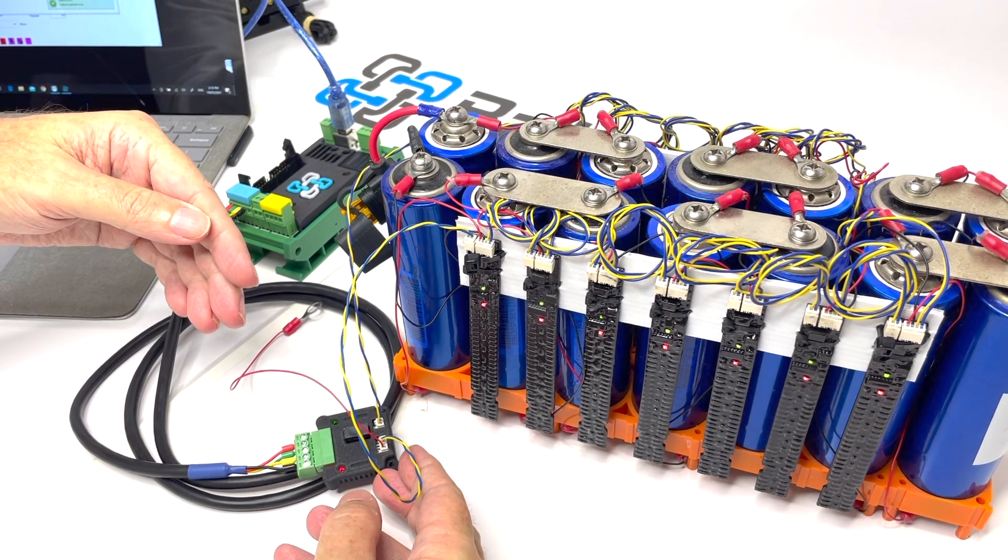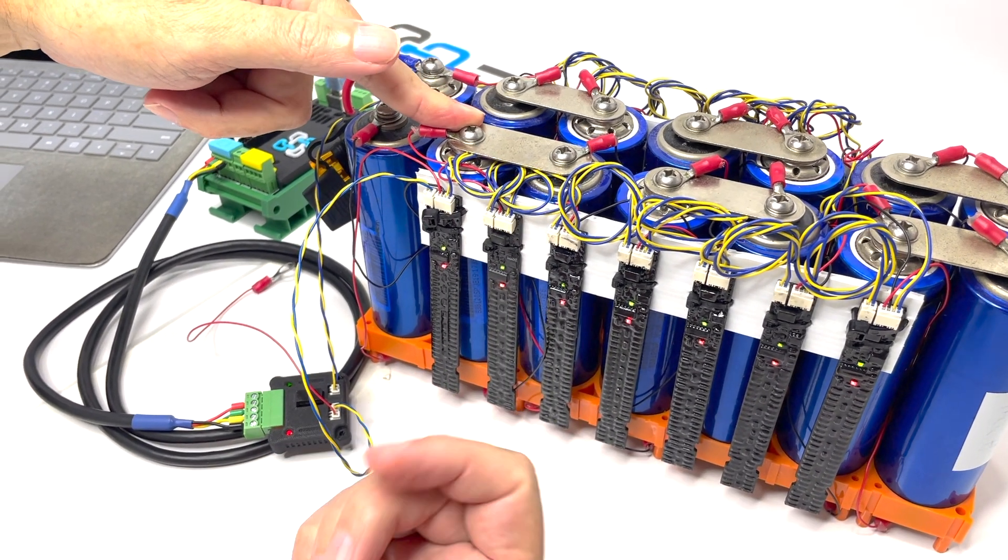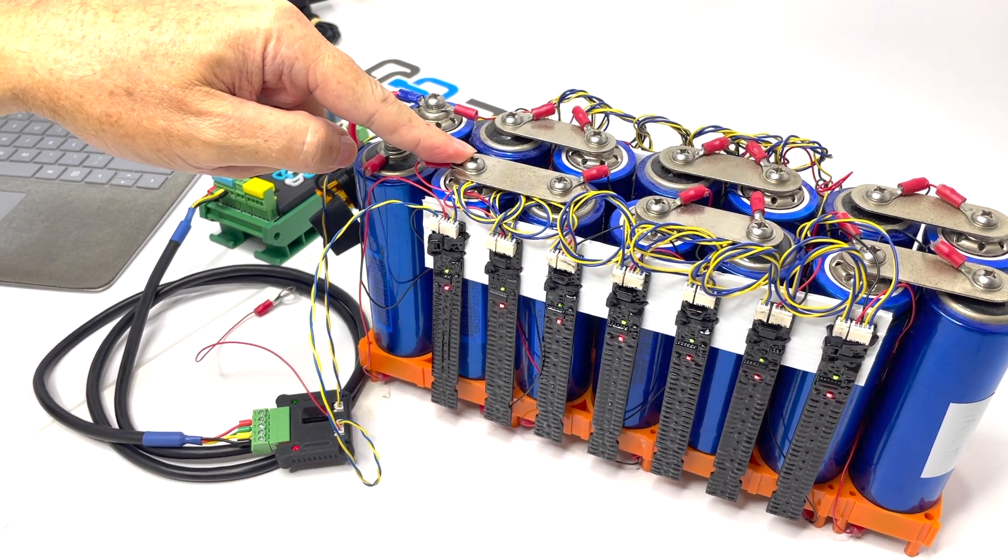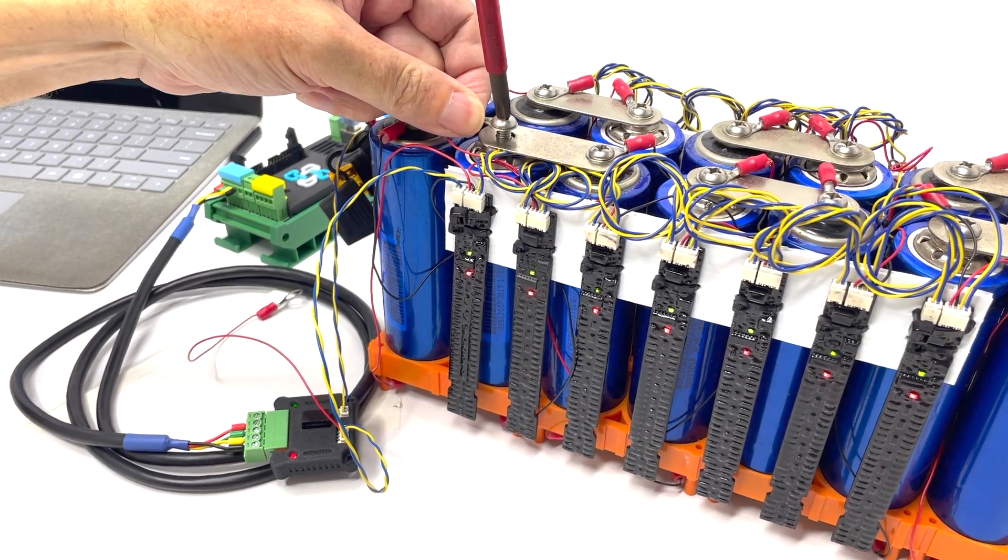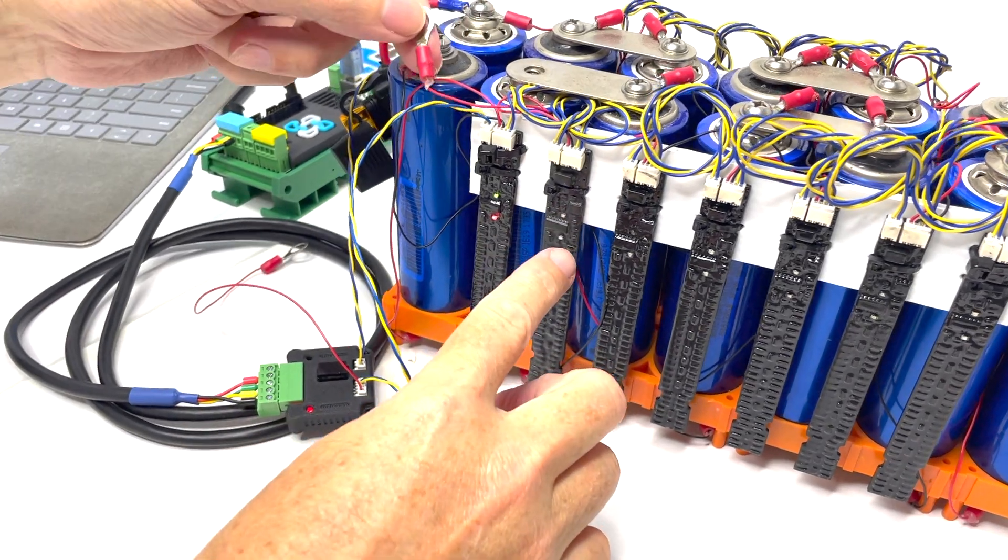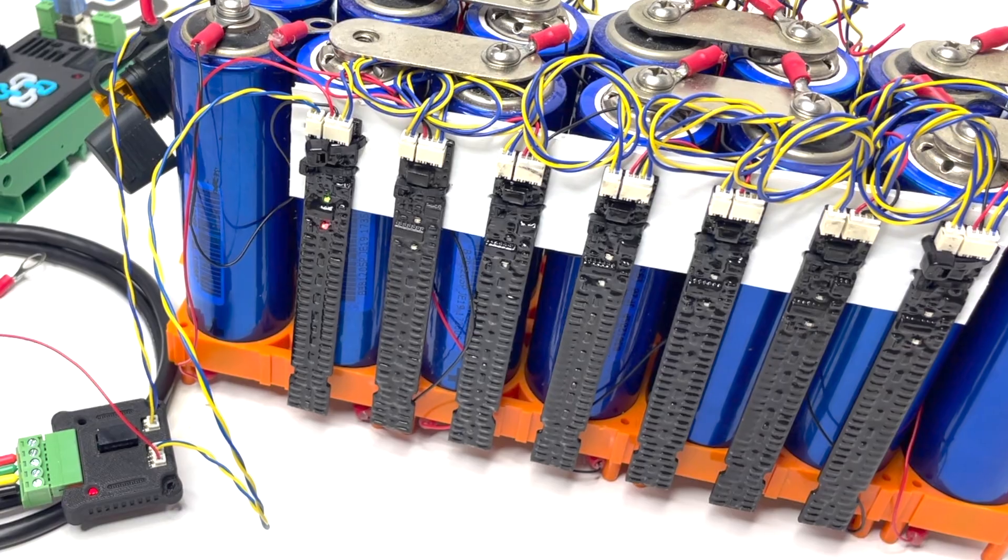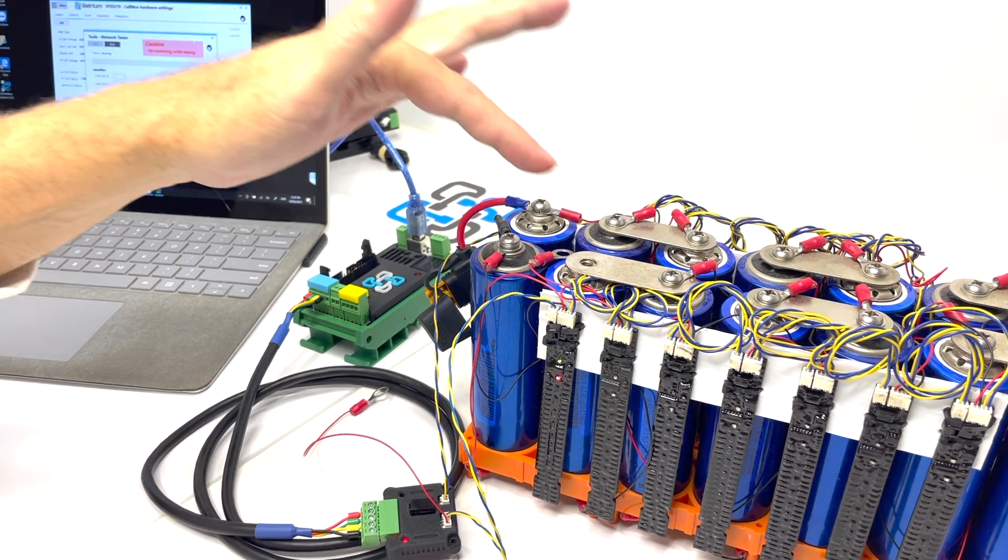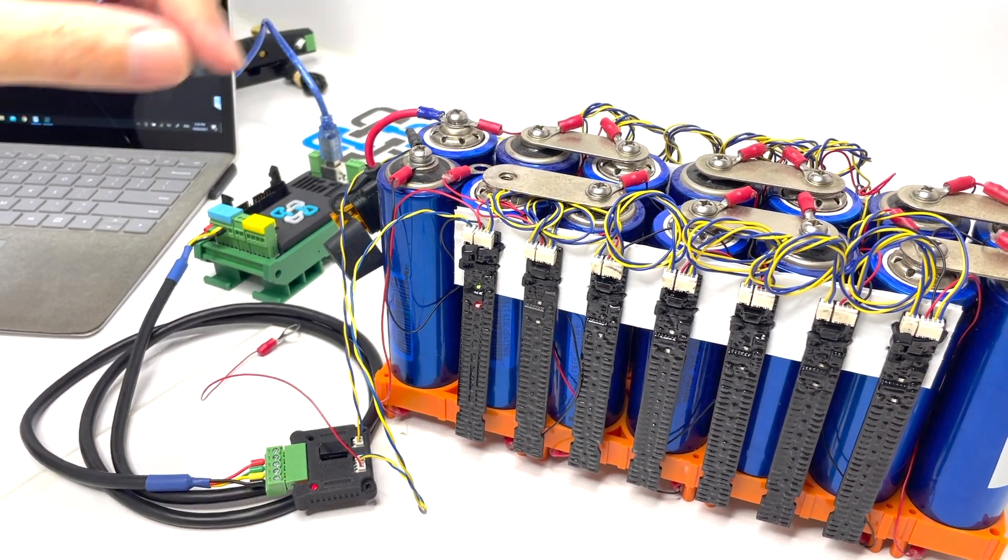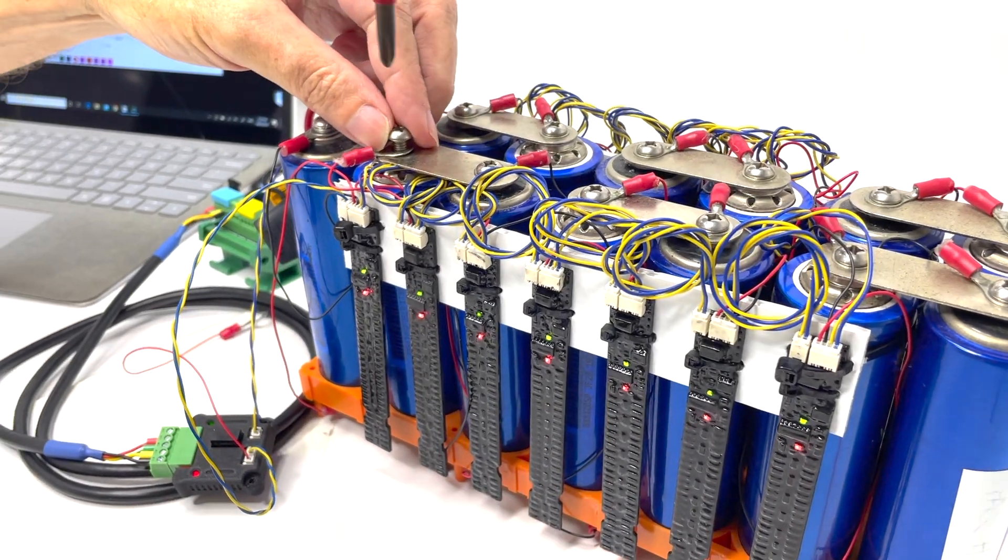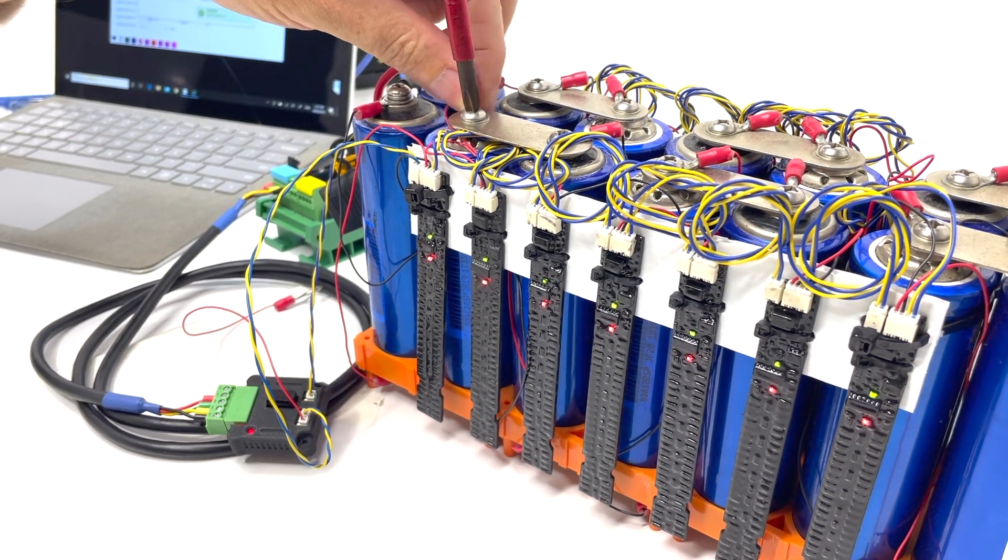If all the cabling's in place, but yet you're still continuing to have a problem, it could be that the second cell here is too low voltage. And we can actually demonstrate this by removing this wire. So we continue to see that we've got the lights. But if this one goes below two volts, then we're not able to actually communicate. So let's just remove this wire. And in this case, you can see that that particular cell monitor has now stopped working. And all the other ones downstream are no longer working. And our network test is also showing us no communication. So in that particular case, we get out a trusty multimeter and just make sure, does that cell measure greater than two volts? If it does, if it's 2.2 volts or greater, we know that there's going to be no issue with the monitor. If there's not, then we might look at some other things and change the wiring loom. But always, if you've got no communication from a point, consider checking the voltages, because if they're below two volts, the cell monitor cannot operate. It hasn't got enough power.